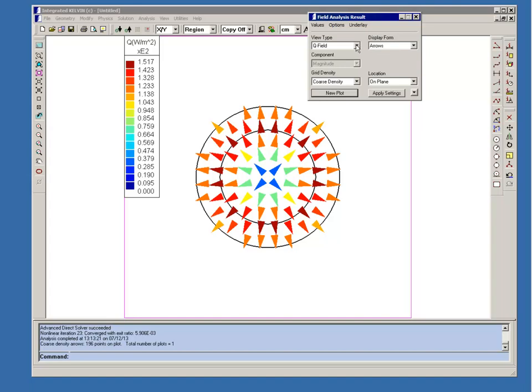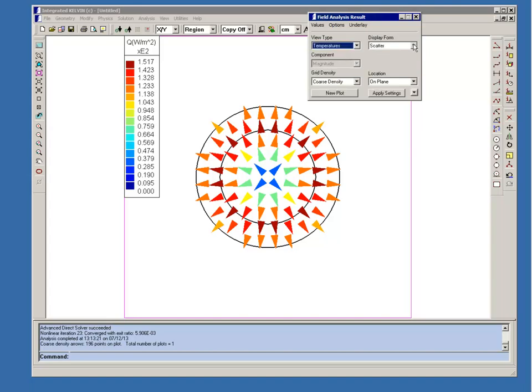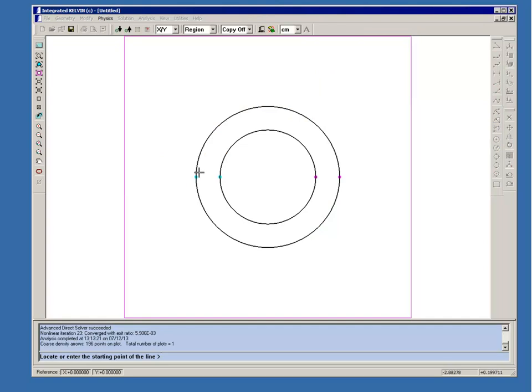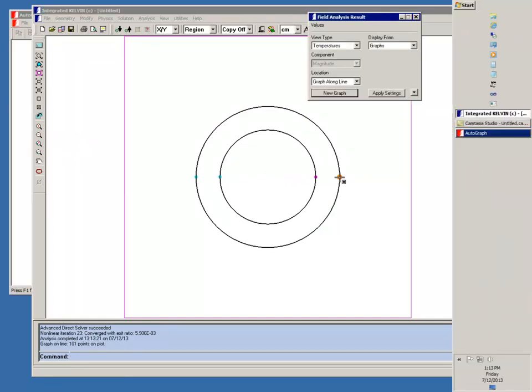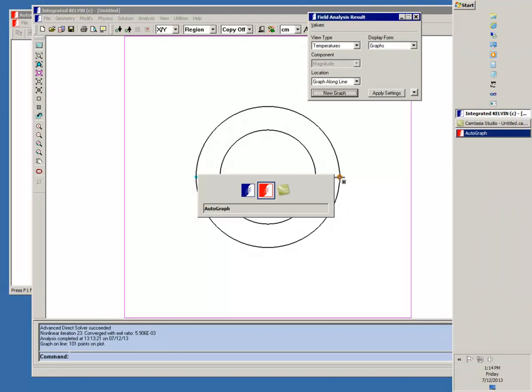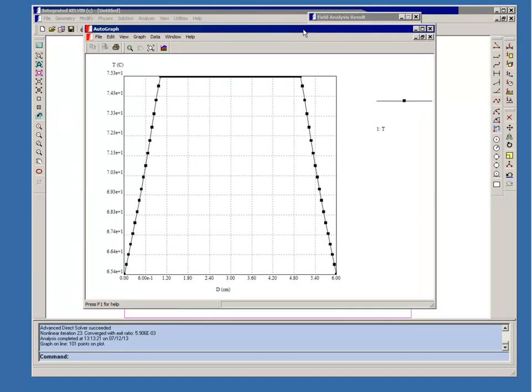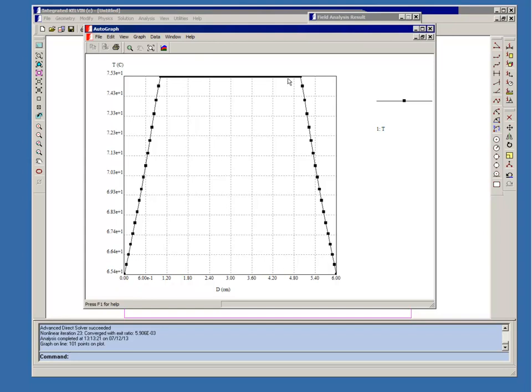We'll also do a plot of the temperature in a graph right through the cable from one edge of the rubber to the other. And this shows an AutoGraph window. We can see that at the edge of the rubber, it's at about 65 degrees. And inside, the temperature throughout the copper is very uniform at 75 degrees.